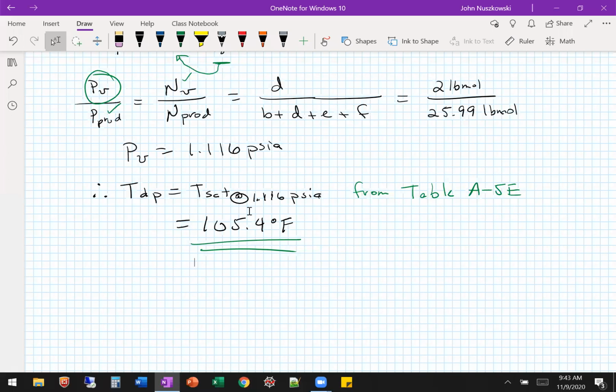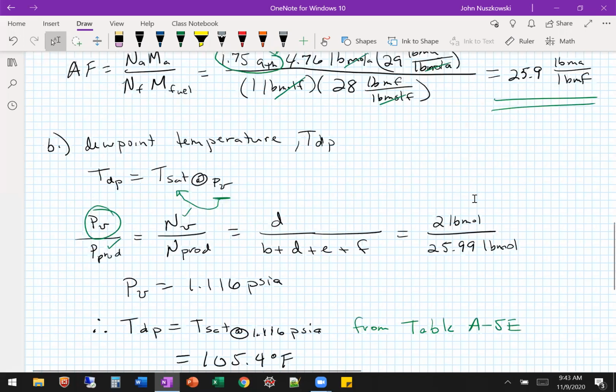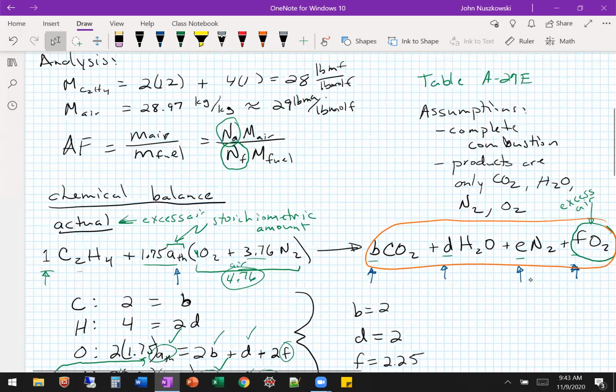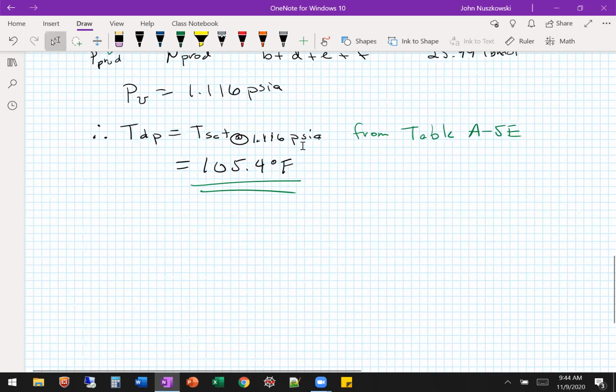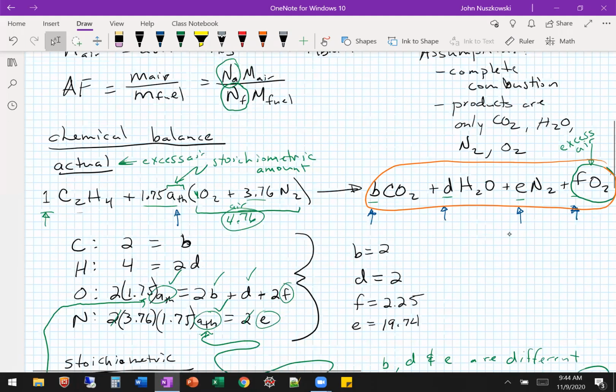In my research, this is very important to know, because if I'm sampling the exhaust to try to get a part of the exhaust and measure these different components, I have to keep the temperature above that. Anything in my sample lines, in my exhaust analyzer where it's measuring it, I have to keep it all above this temperature, and usually much higher above it, because you want to be careful. So then the water doesn't drop out, because if the water drops out, you're going to get different measurements, because it doesn't measure the moles, it measures the mole fractions when you have an analyzer.